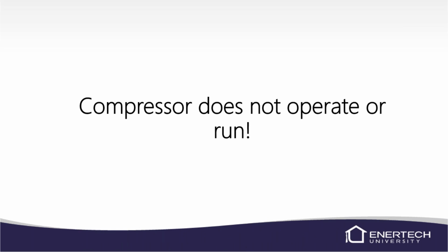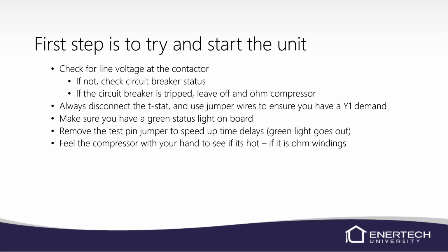So if the compressor doesn't run, it doesn't operate, there's no amp draw on the compressor, the contactor may be pulled in or not, but it's not running. So the first thing we're obviously going to do when a compressor is not running is look for line voltage at the contactor. Obviously, if there's no power there, we probably don't have a status light on the lockout board. That's usually a good indication that there's no power coming into the unit. So check the circuit breaker, obviously check your voltage coming into your contactor.